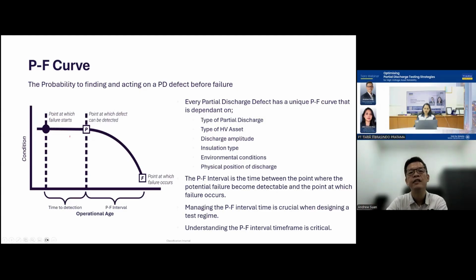Okay. And then the physical position of the discharge. You want to know where exactly the discharge happened. Is it in the circuit breaker, or in the VT or CT chamber, or in the cable termination? These are the six points we think are good for you to find out, because they contribute to the P to F interval, how fast the switchgear or the transformer will fail. So once you understand this, you will be able to plot out the P to F interval time frame.